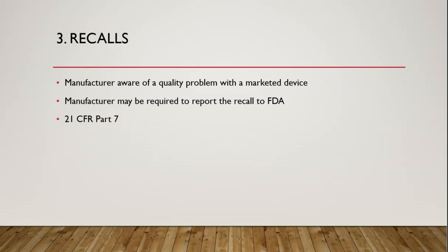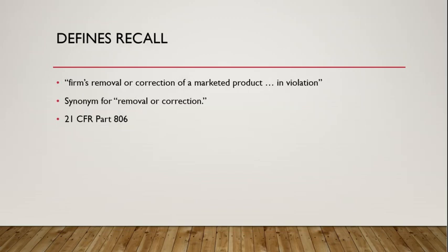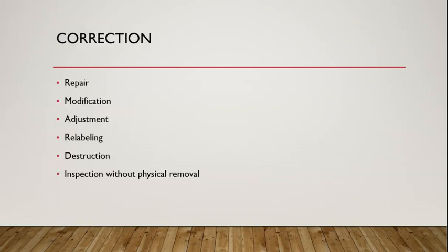Let's take a look at what a recall actually is. It's the firm's removal or correction of a marketed product that appears to be in violation of the FDA Act. And recall is a synonym for removal or correction. And I put that citation for you in the third bullet point. When we drill down in the definition of correction, we see ever so many dimensions. Correction can be a repair, a modification, an adjustment, a relabeling, destruction, or an inspection without physical removal.